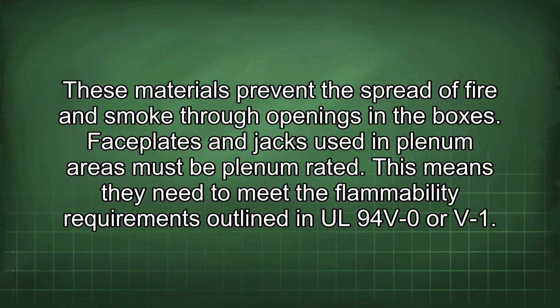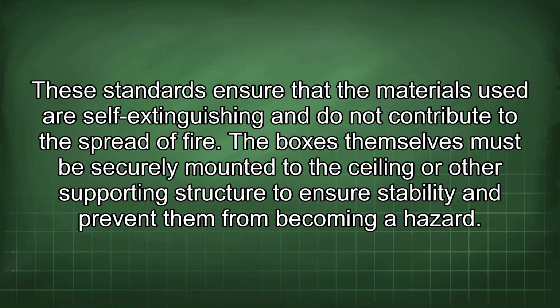Faceplates and jacks used in plenum areas must be plenum rated. This means they need to meet the flammability requirements outlined in UL 94 V0 or V-1. These standards ensure that the materials used are self-extinguishing and do not contribute to the spread of fire.